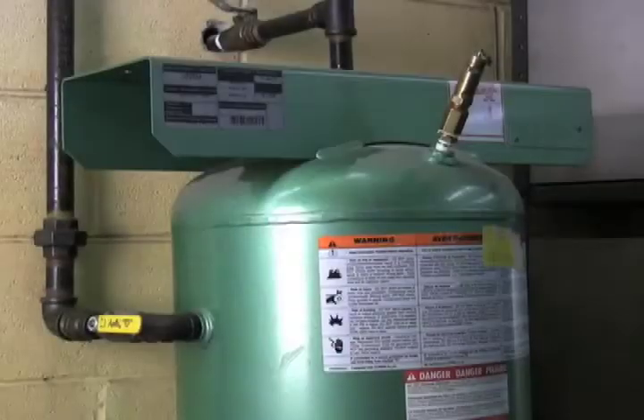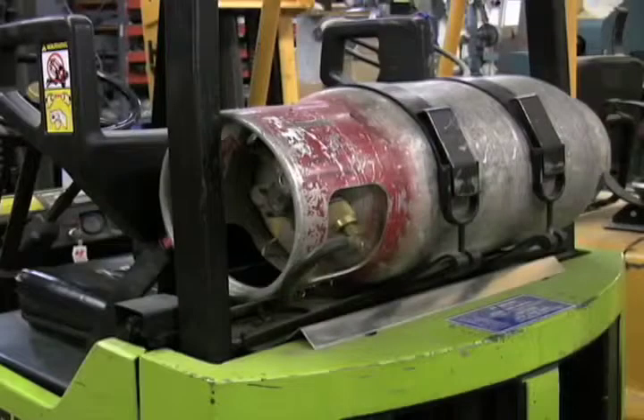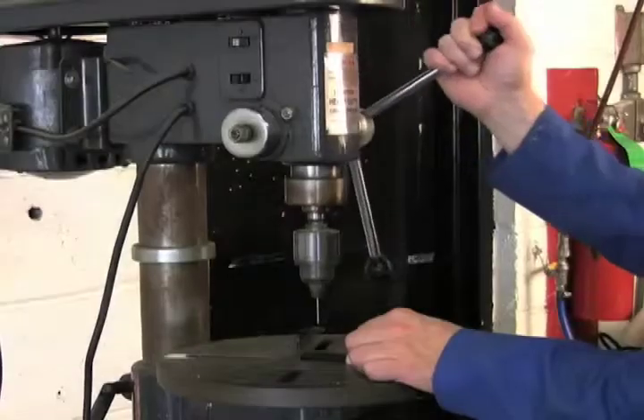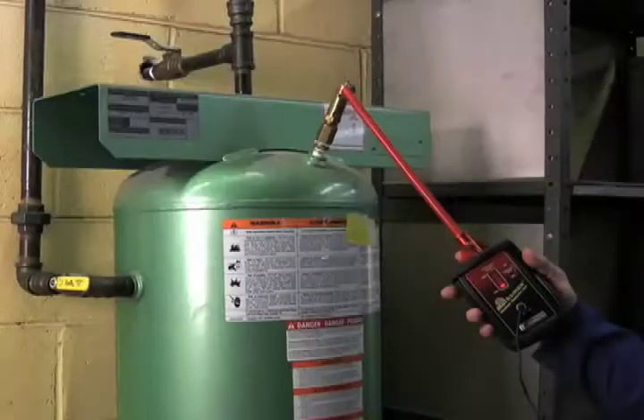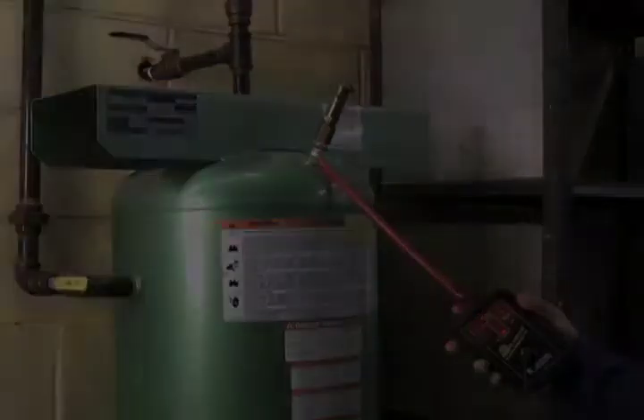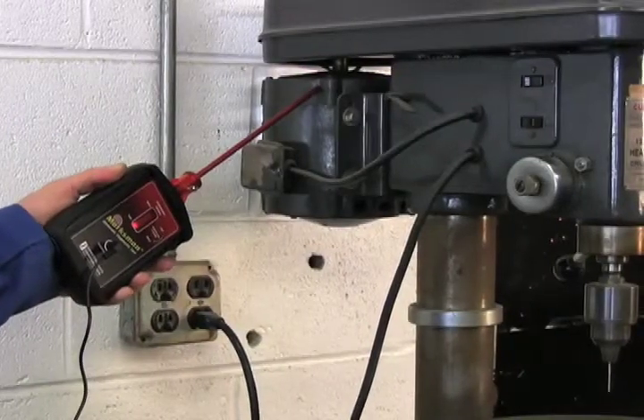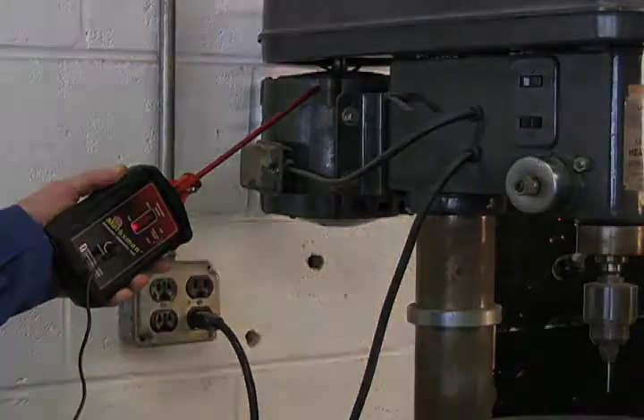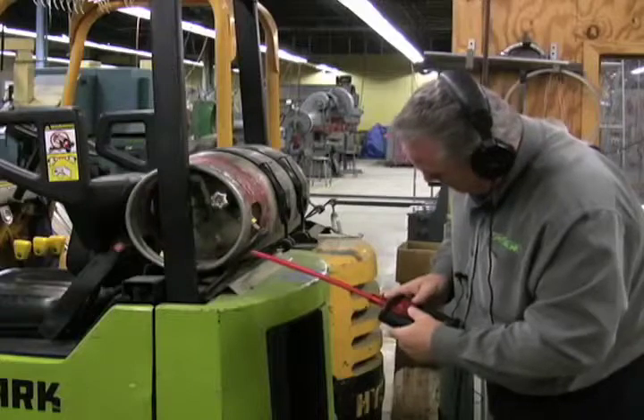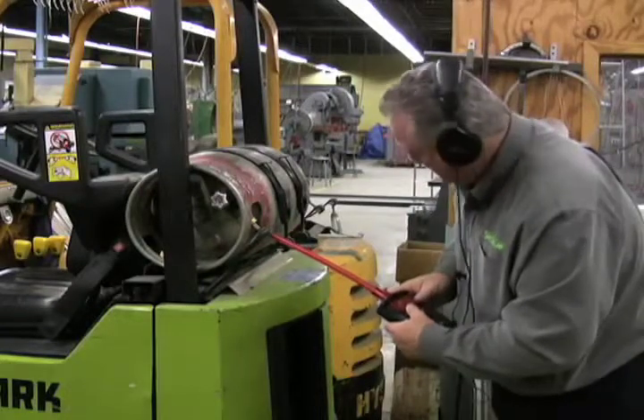The Marksman operates on a principle of physics that says pressurized leaks and moving parts will always emit sound because of the friction they generate. Unfortunately, when these leaks are very small or the wear on parts is in its beginning stages, this sound is in the high frequency ultrasonic range, making it inaudible to the human ear.